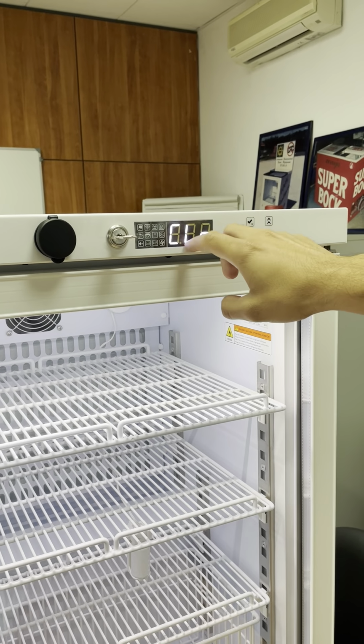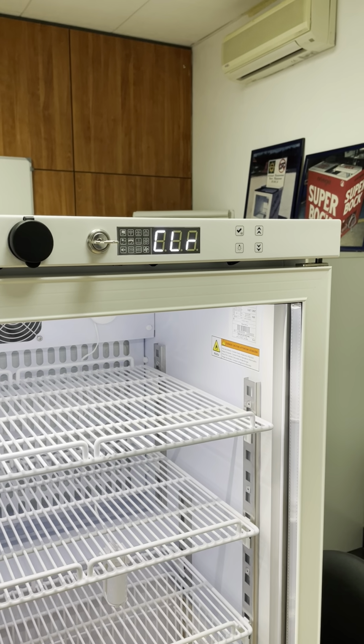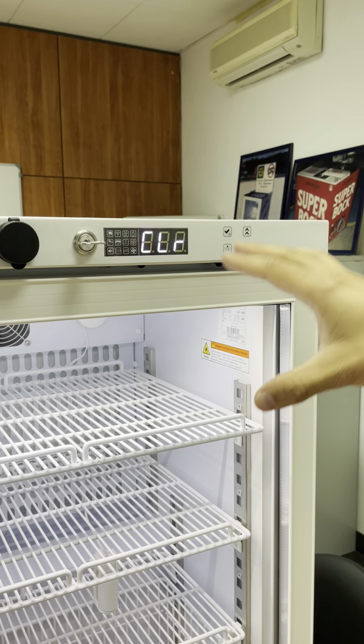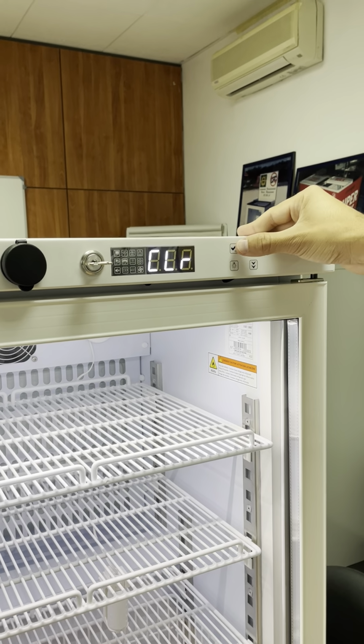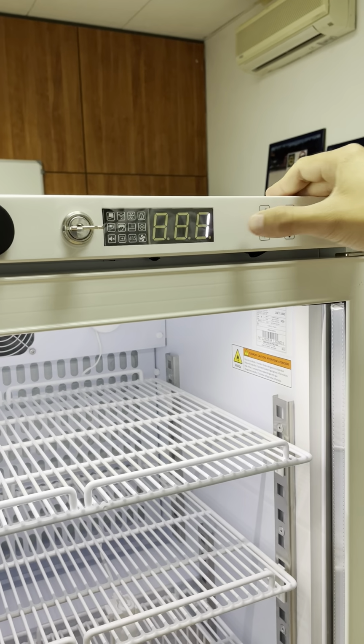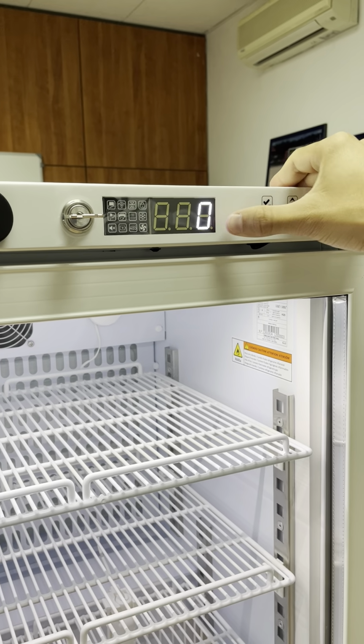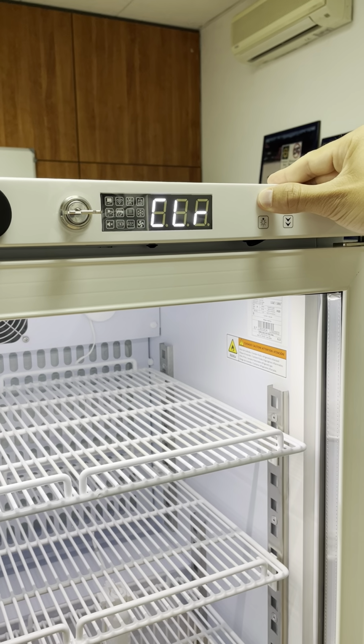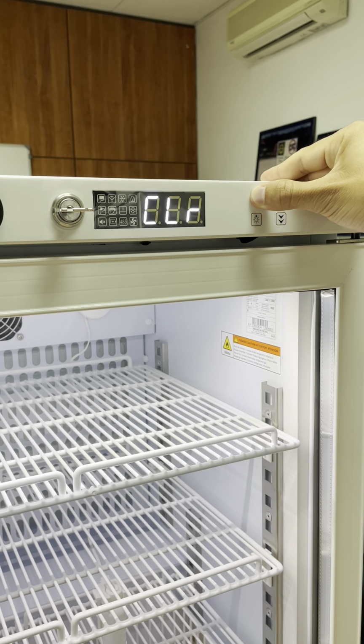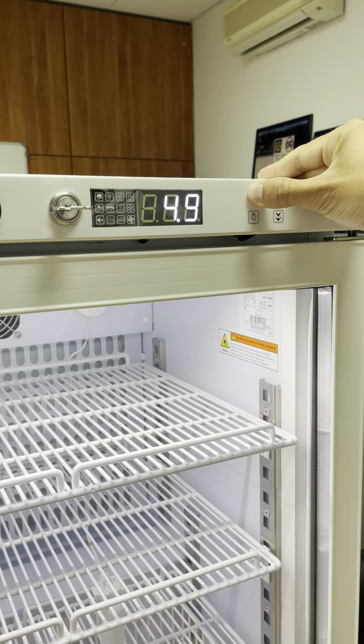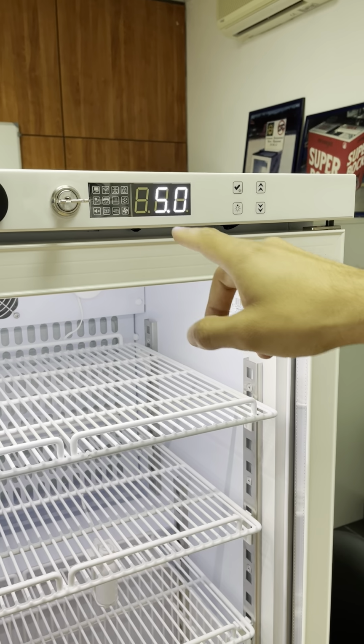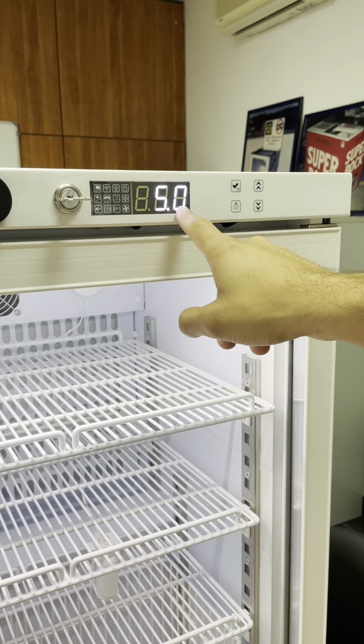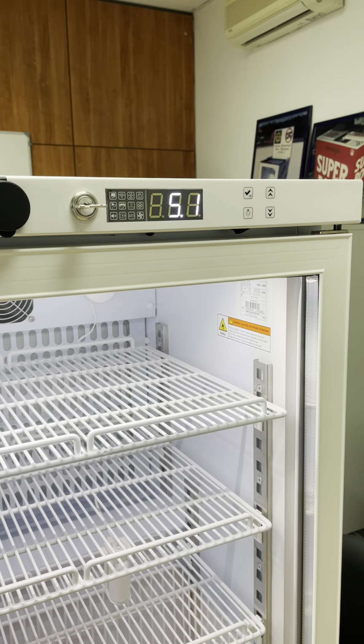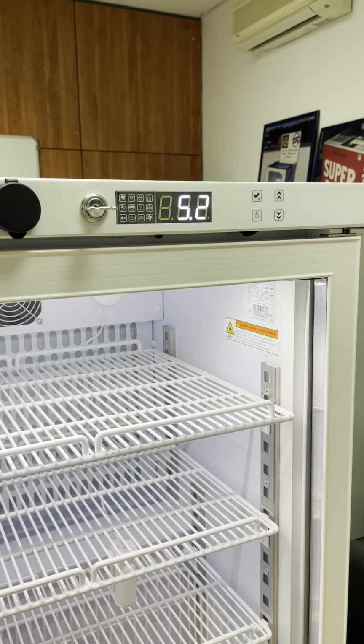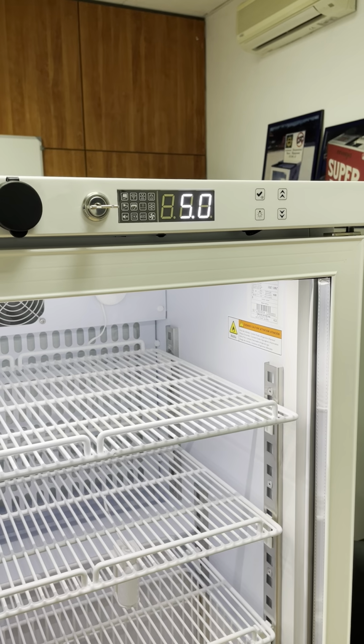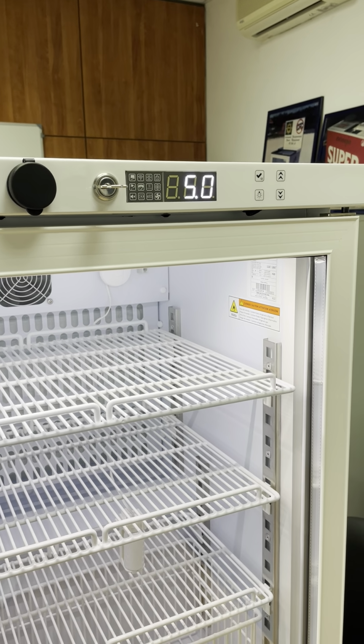But first I will clear. So it means that I accept that I already know that there was a problem in the equipment and I need to check. So you go clear. Where it is 1, you pass to 0, and you set again. Wait for the noise. Okay, and now it's clear. You will not have the UH1 again, because you already accepted, you acknowledged that you saw that there was an alarm and that you will do something about this.